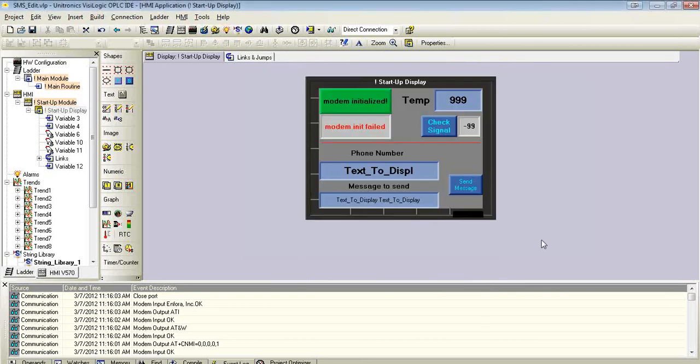And I'm going to unplug the DB9 cable from the modem. And now I'm going to attach the MJ1022CS72. That's the DB9 adapter that came with it. And I'm going to connect a serial cable from there to port 2 in my PLC. For today's example, I have a Vision 570. Let's go ahead and take a look at the ladder.